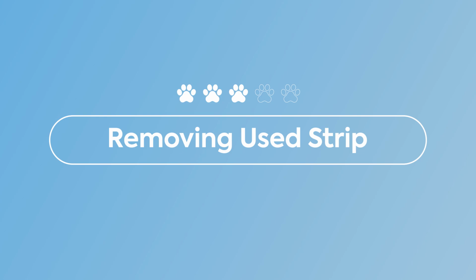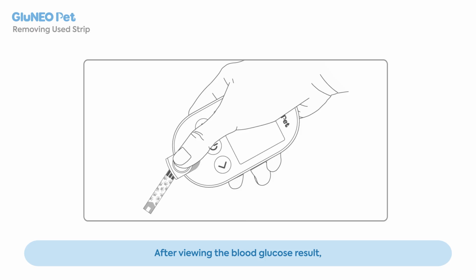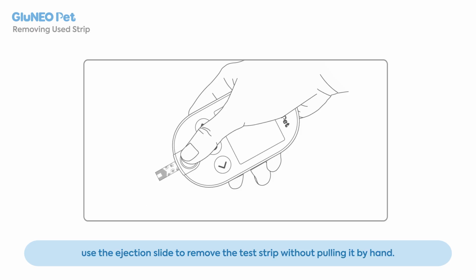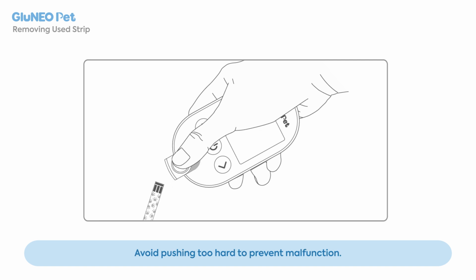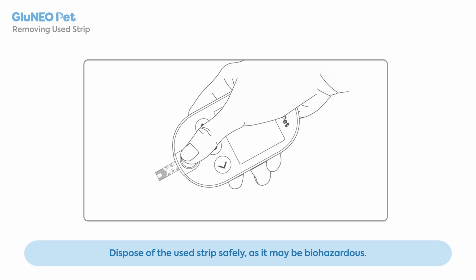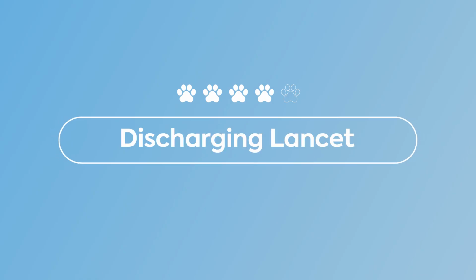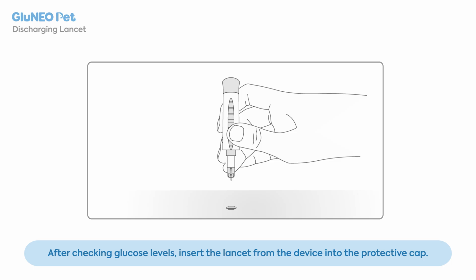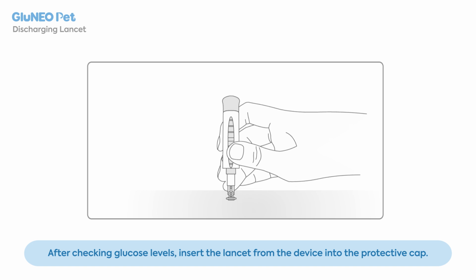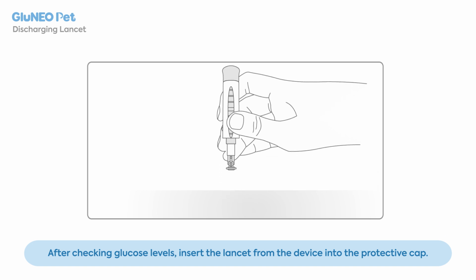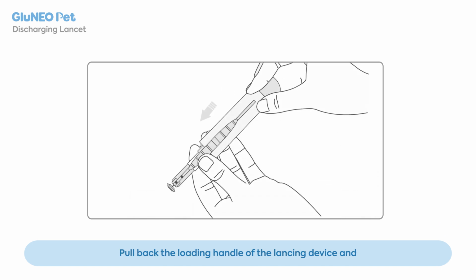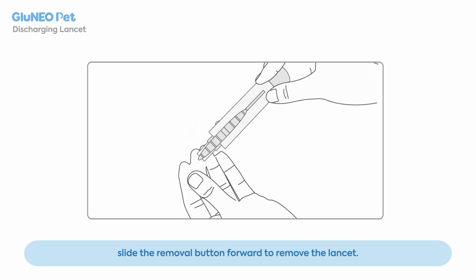Let's look at how to remove a used strip. After viewing the blood glucose result, use the ejection slide to remove the test strip without pulling it by hand. Avoid pushing too hard to prevent malfunction. Dispose of the used strip safely, as it may be biohazardous. Check local guidelines for proper disposal. Let's discover how to discharge the lancet. After checking glucose levels, insert the lancet from the device into the protective cap. Pull back the loading handle of the lancing device and slide the removal button forward to remove the lancet.